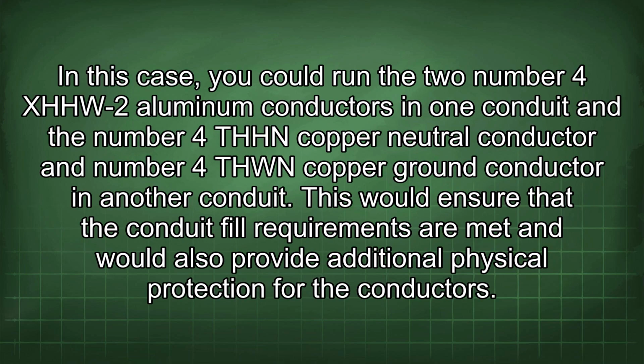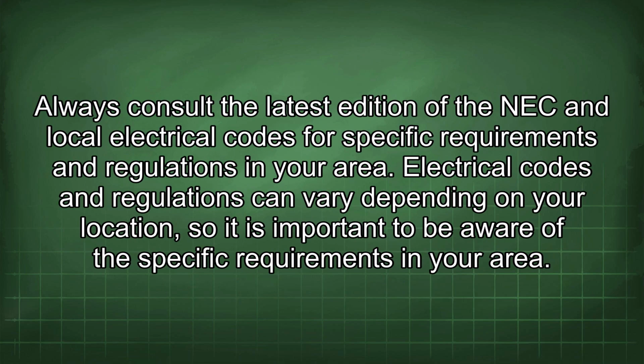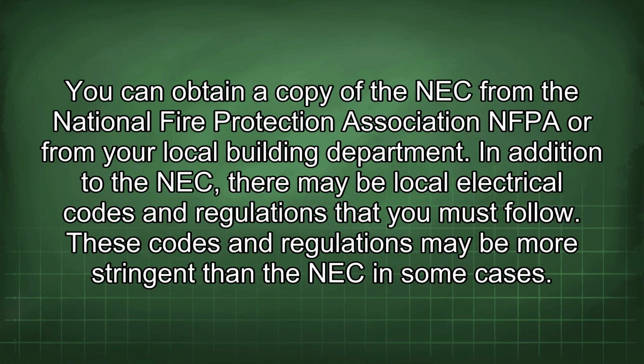In this case, you could run the two number 4 XHHW-2 aluminum conductors in one conduit and the number 4 THHN copper neutral conductor and number 4 THWN copper ground conductor in another conduit. This would ensure that the conduit fill requirements are met and would also provide additional physical protection for the conductors. Always consult the latest edition of the NEC and local electrical codes for specific requirements and regulations in your area. Electrical codes and regulations can vary depending on your location, so it is important to be aware of the specific requirements in your area. You can obtain a copy of the NEC from the National Fire Protection Association (NFPA) or from your local building department.